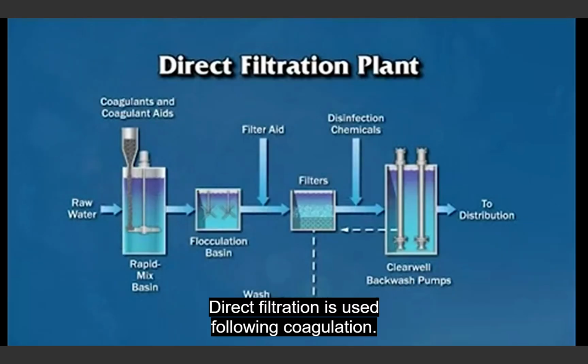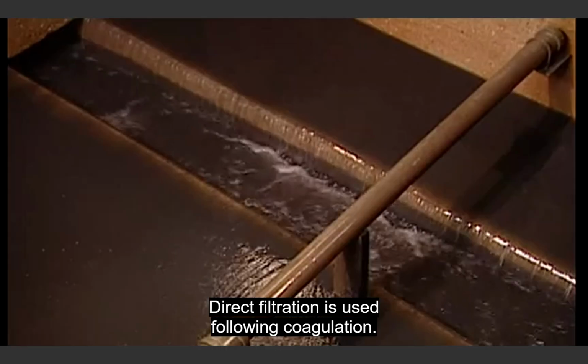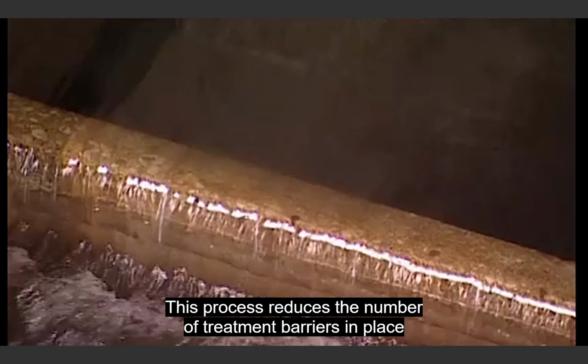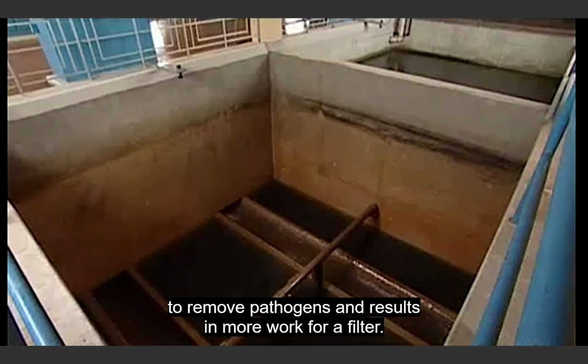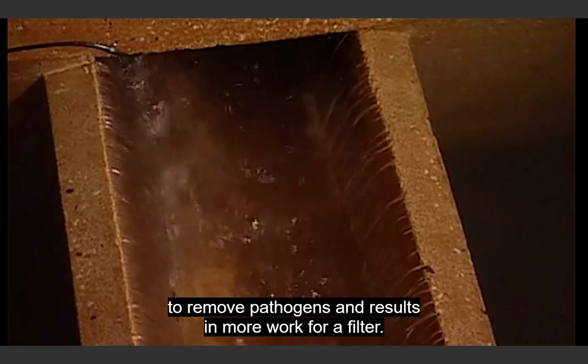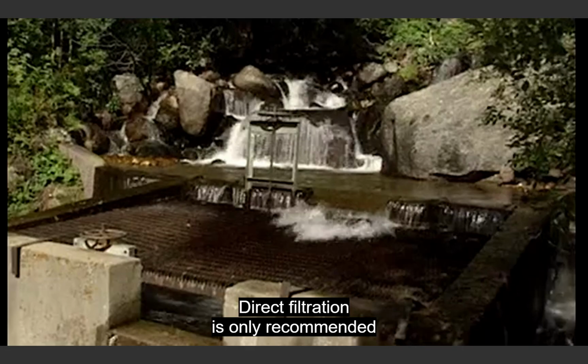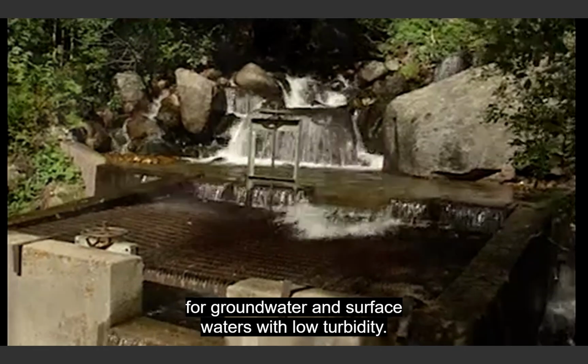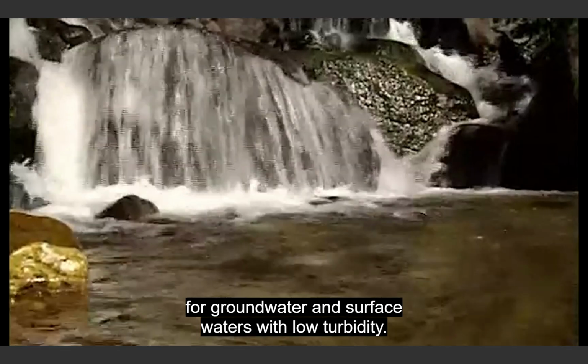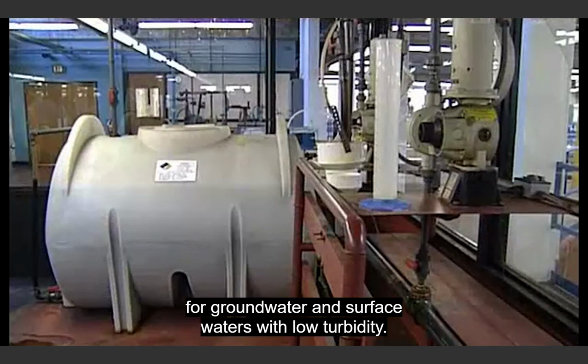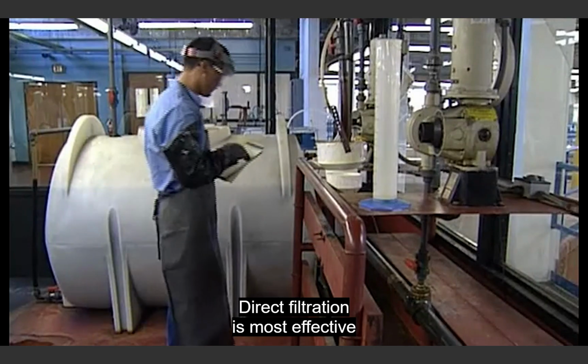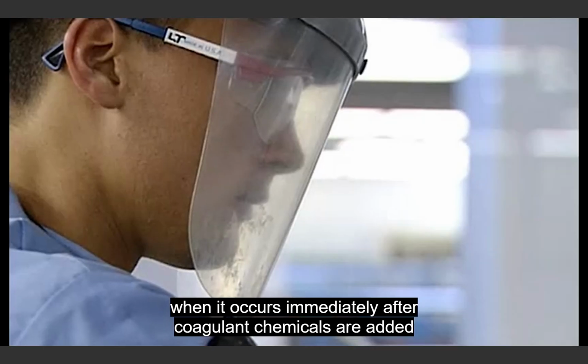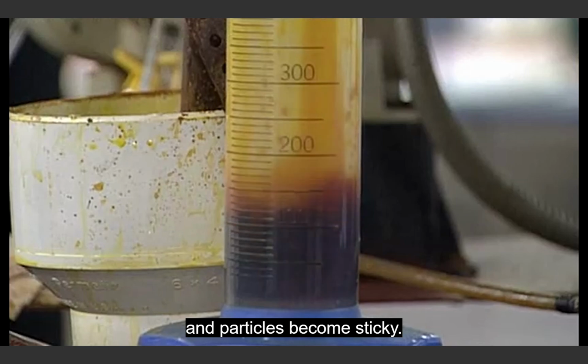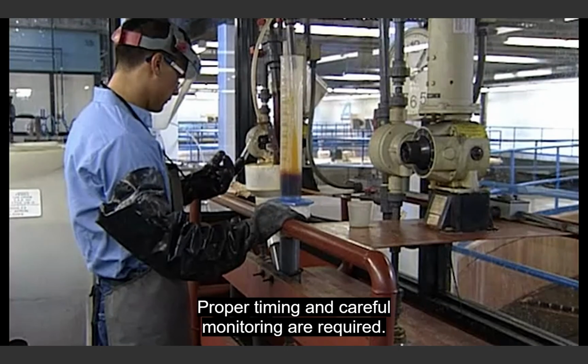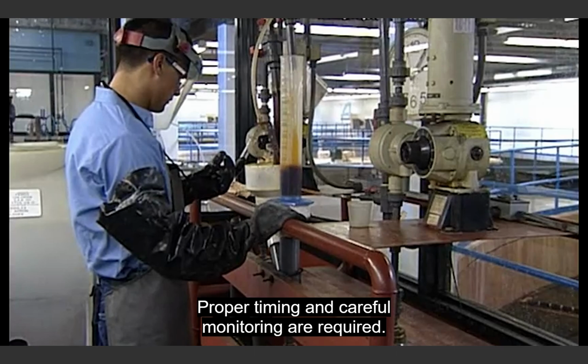Direct filtration is used following coagulation. This process reduces the number of treatment barriers in place to remove pathogens and results in more work for a filter. Direct filtration is only recommended for groundwater and surface waters with low turbidity. Direct filtration is most effective when it occurs immediately after coagulant chemicals are added and particles become sticky. Proper timing and careful monitoring are required.